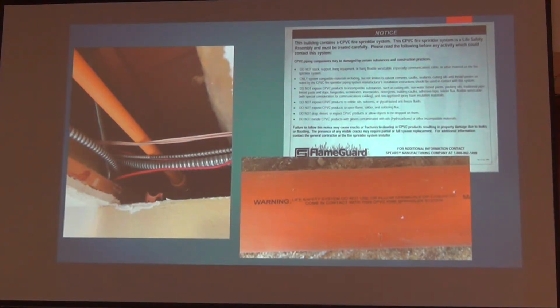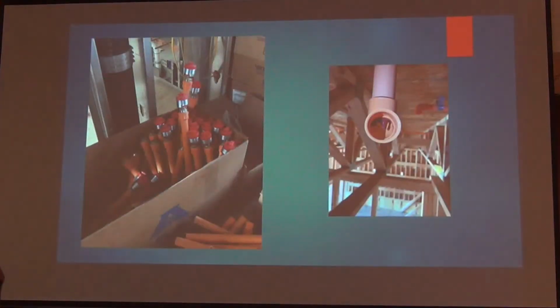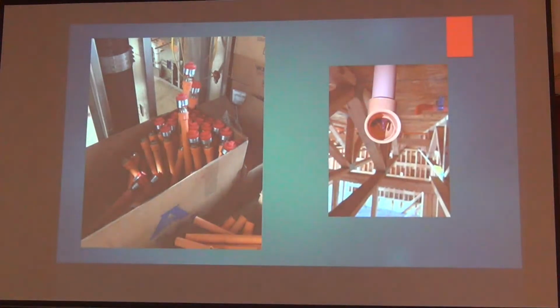As you're walking through your job sites, make sure to look at all of the piping that they're putting together. Oh, I did include a picture of it. Good, that'll be the next slide. Look at the piping that they're putting in, because if you walk up there and you see something like this, automatically that's a fail. Sprinkler manufacturers will not, number one, stand behind any heads that are not installed on the pipe in the air, because they're subject to damage.